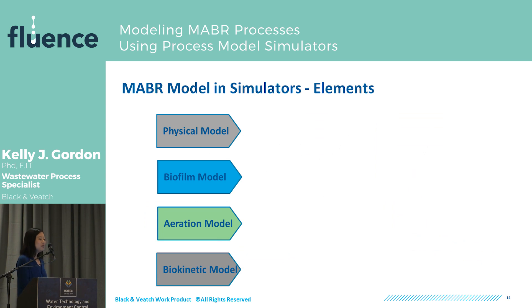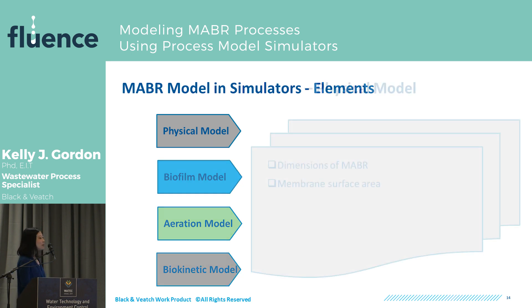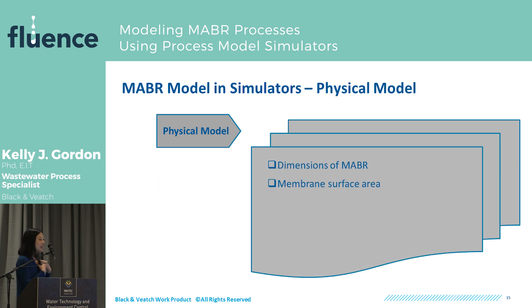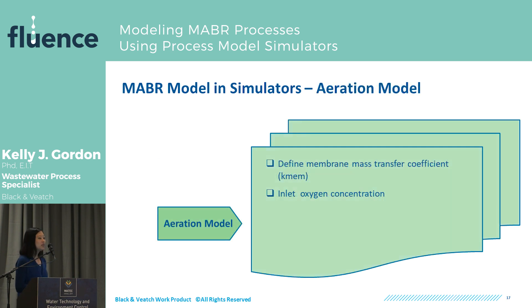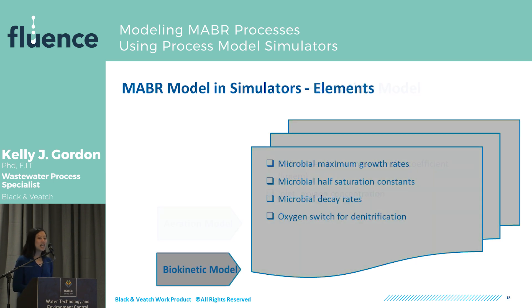Within this one-dimensional biofilm subunit in GPSX, we can categorize the physical model, the biofilm model, the aeration model, and the biokinetic model. The parameters needed include: for the physical model, the dimensions of the MABR and the membrane surface area. For the biofilm model — these parameters are harder to get at — we need the liquid diffusion layer thickness, biofilm thickness, dry weight, rate of attachment and detachment, diffusivities within the biofilm, and solids exchange rate. For the aeration model, we need the mass transfer coefficient across the membrane material and the inlet oxygen concentration. For the biokinetic model, we want to know the kinetic and stoichiometric rates of each microbial process we're trying to capture.